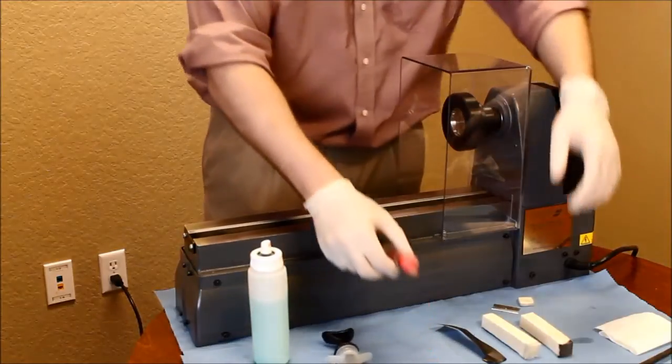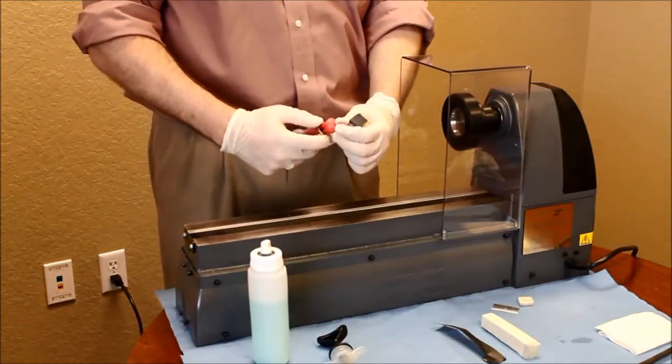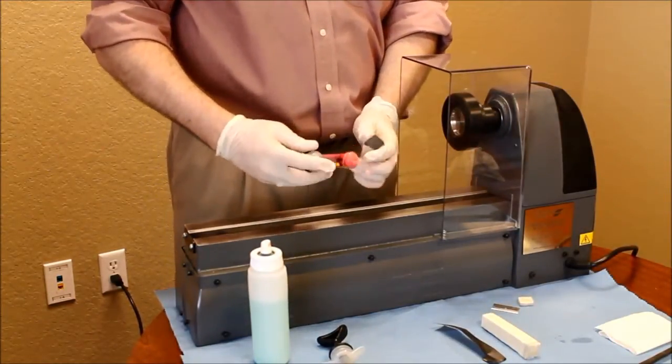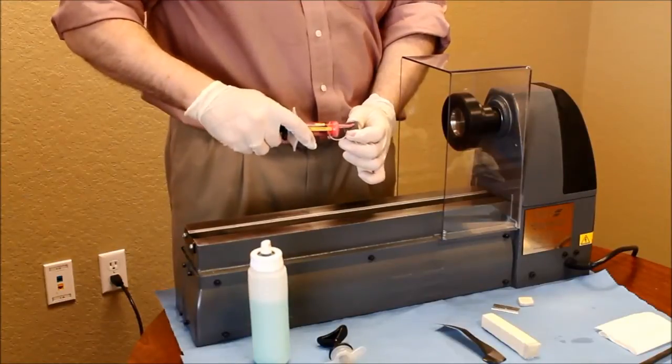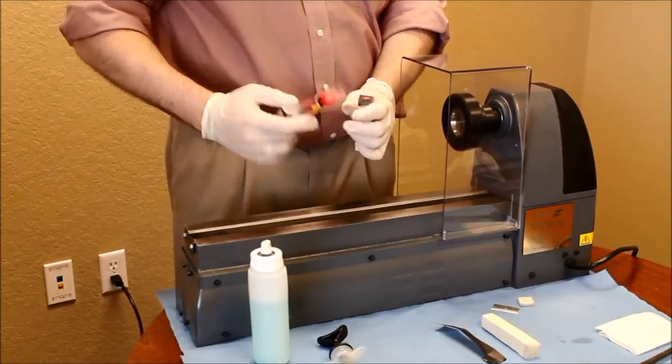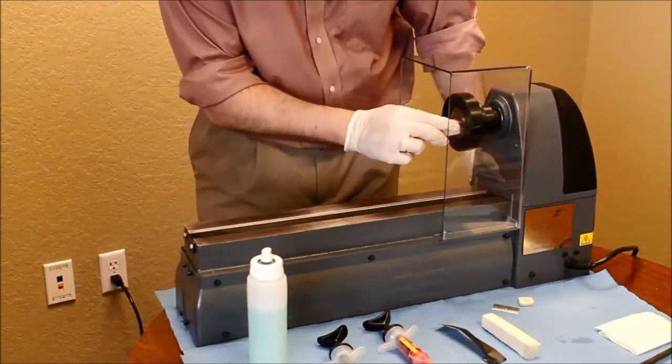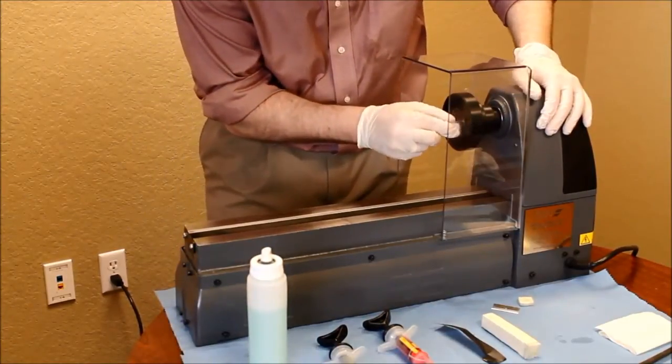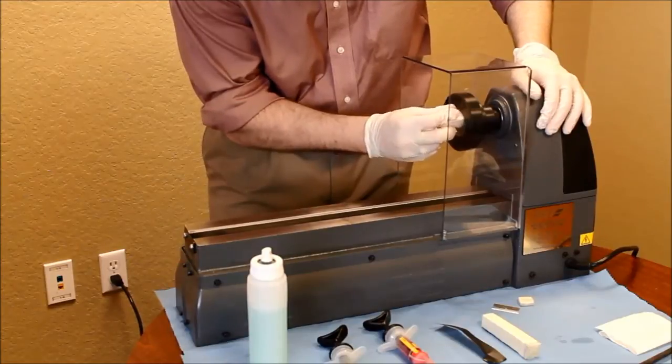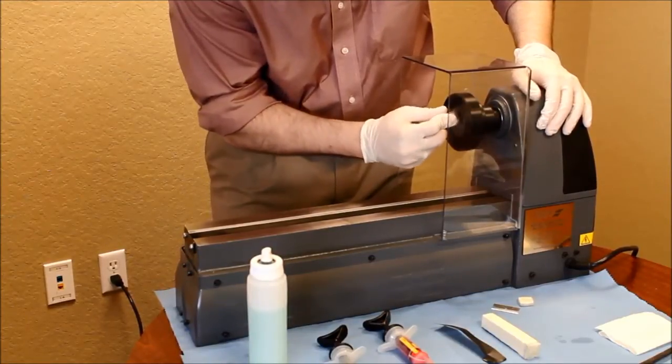Apply the 8 micron diamond compound to a hard grinding stick coating with oil and, if necessary, stopping the lathe to apply. Ensure to grind from the center outwards, keeping even pressure applied, and once complete, remove the polishing content with a soft cleaning stick.